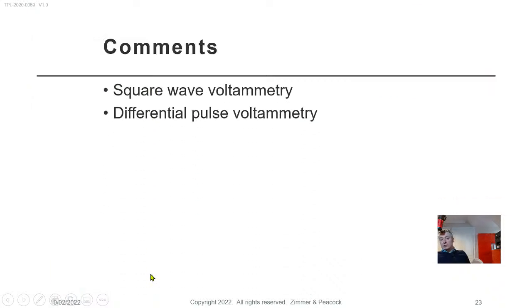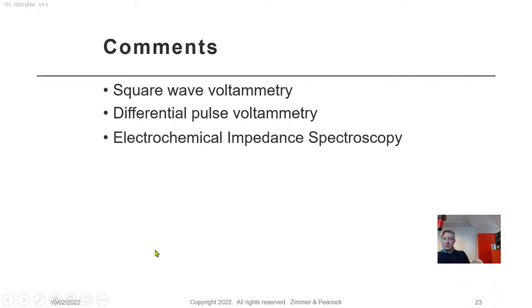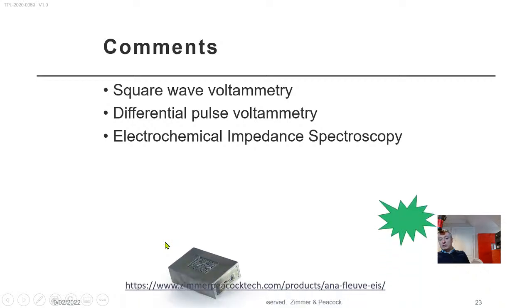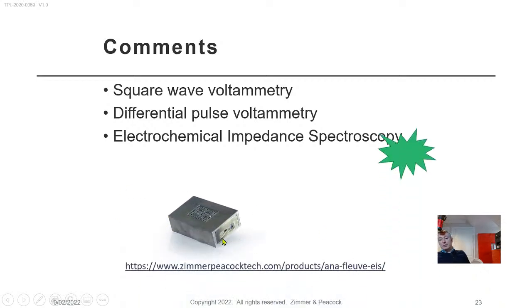So we do like square wave voltammetry to do immunosensors. We do like differential pulse voltammetry. We do like impedance spectroscopy. And I actually prefer these days, if you're making immunosensors, to use EIS. The only thing about EIS is the instrument, unfortunately, is about twice as much as the non-EIS instrument. So that's why I say Anapot is good for most, 90% of what I've talked about today. But if you really want to do EIS, then you'll have to use the Anapot EIS.